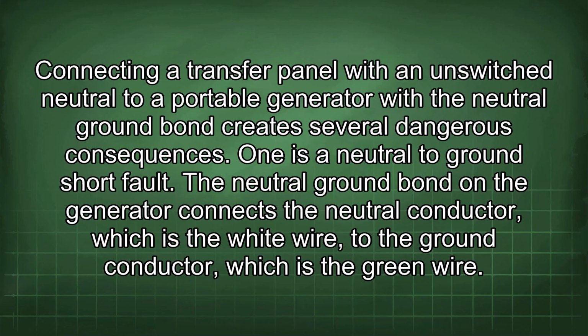Connecting a transfer panel with an unswitched neutral to a portable generator with the neutral ground bond creates several dangerous consequences. One is a neutral to ground short fault. The neutral ground bond on the generator connects the neutral conductor, which is the white wire, to the ground conductor, which is the green wire.